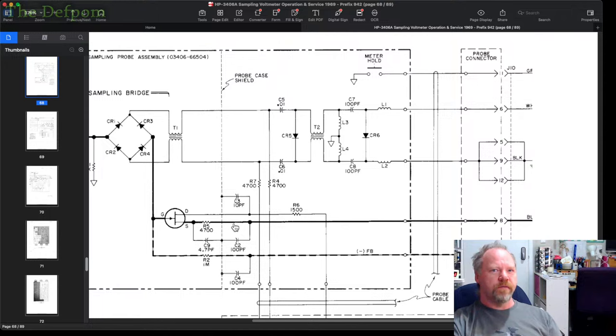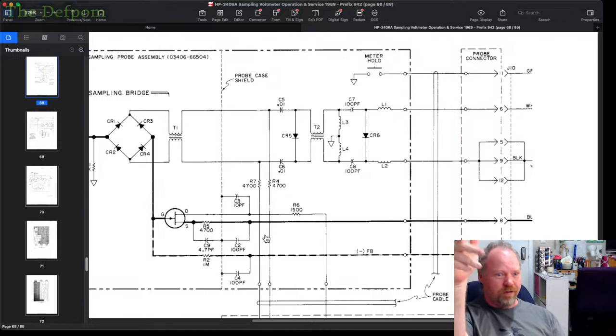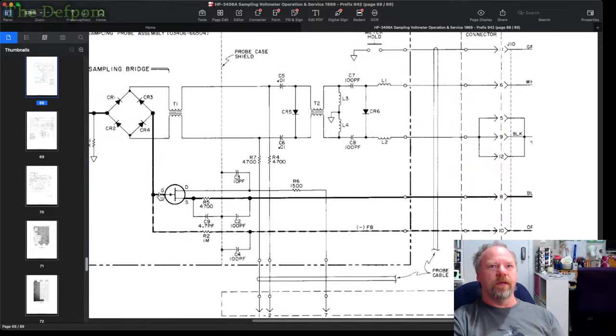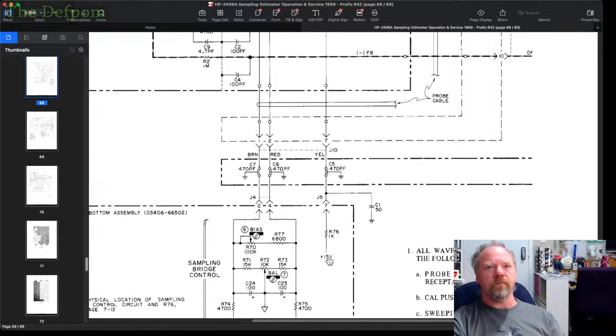Now the interesting thing is the feed for this FET. You've got the source there, which goes back as the input with these capacitors and so on. One thing I did think of is maybe there's an earthing problem, and this earth wasn't connected, so all these capacitors are effectively linked together with no grounding, which could have been causing a bypassing through the system. But I've already ruled that out. I thought it could be an earth problem, because there are little contacts inside the probe which touch the probe body. If they're not bent out enough, because they've gone weak, and no longer touch the probe body, it could mean it's not actually grounded, and the capacitors are basically joining bits of circuitry together. But it wasn't that. Anyway, the drain for that FET comes back down here, down to a 15-volt supply.